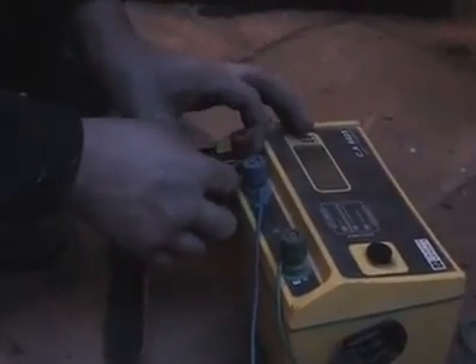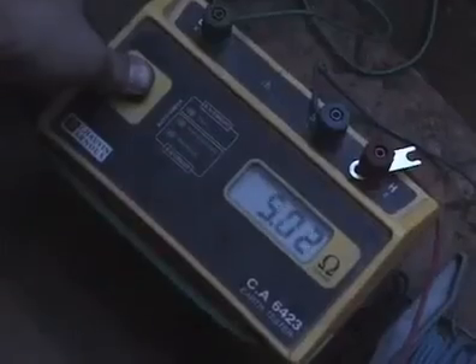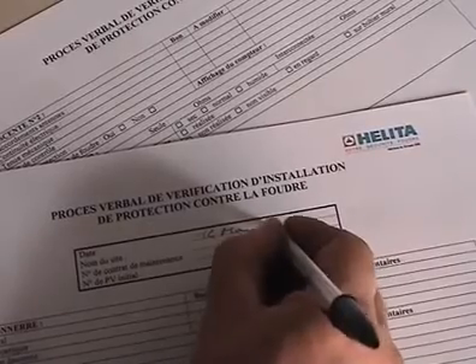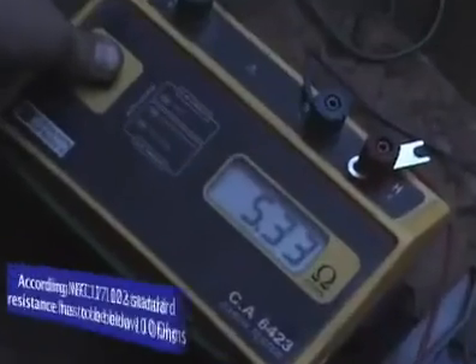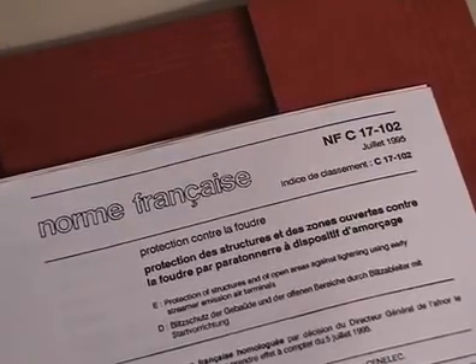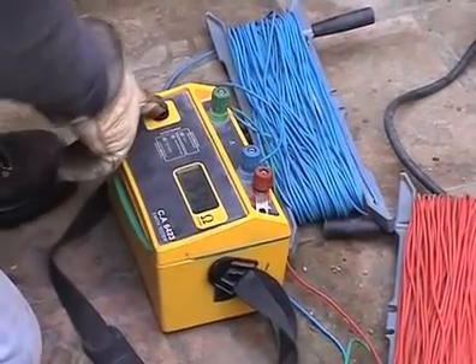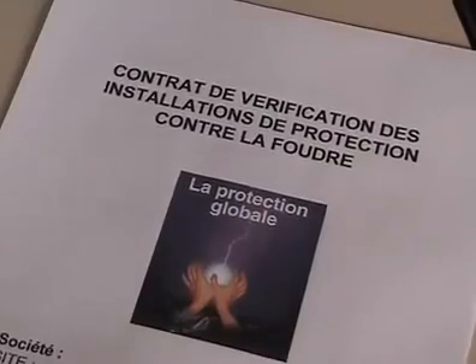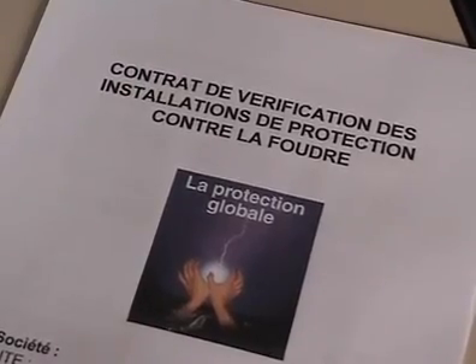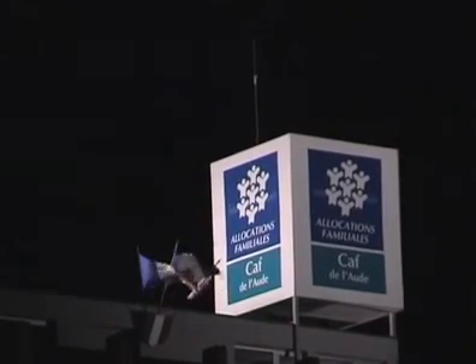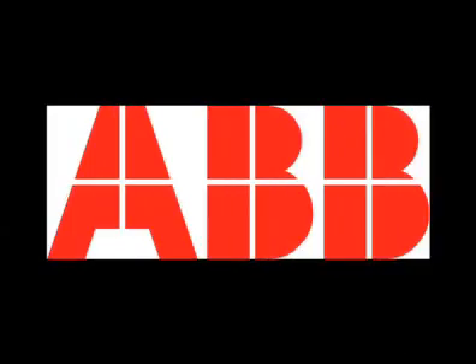A final test is conducted to verify that the installation was done correctly in presence of the client and the installer. Remove the test coupling to be able to conduct the earth measurement and indicate this value on the conformity certificate. The NFC 17102 standard requires that all sites protected by early streamer emission lightning rods must be verified on a continuous basis. It is recommended that a maintenance contract be signed between the customer and the authorized installer to facilitate this approach.